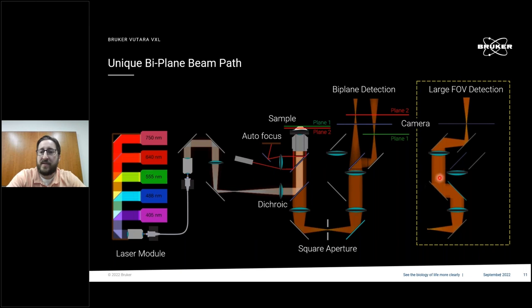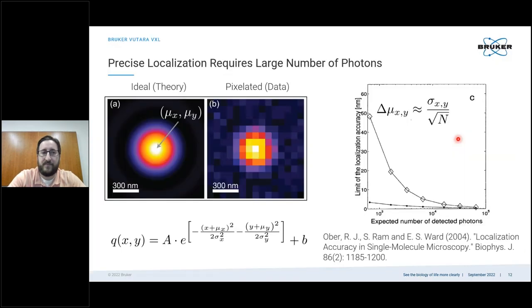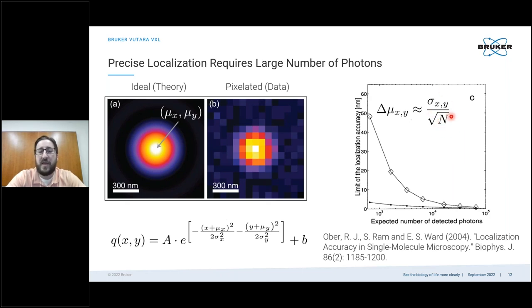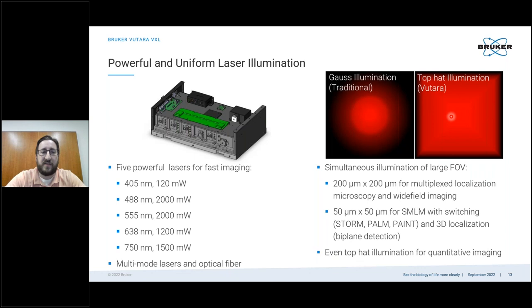Also shown is our bypass imaging mode, where two mirrors slide into place to bypass the biplane module and provide a larger field of view projection. As Winfried mentioned, since single molecule localization is fundamentally a fitting routine applied to pixelated data — rather than image formation like a typical microscope — the ultimate resolution achievable is fundamentally determined by the number of photons collected, in a one-over-square-root relationship. This has several design implications for the instrument. The first is that we use five powerful laser lines to provide bright images and facilitate fast imaging.